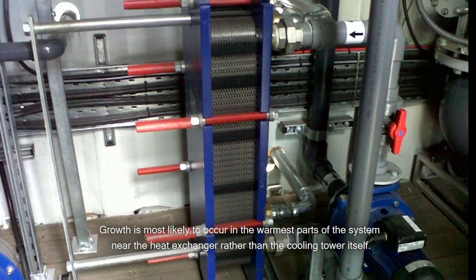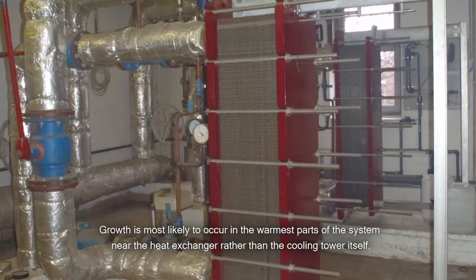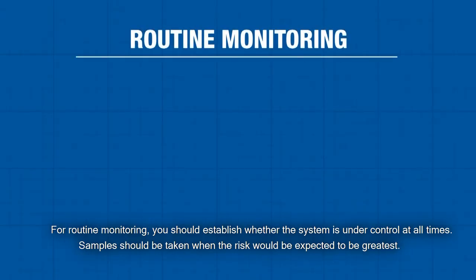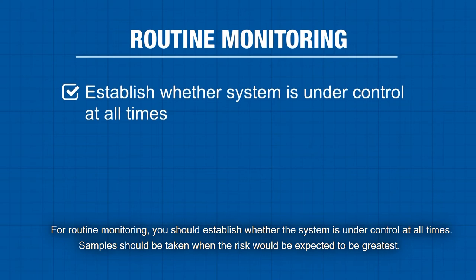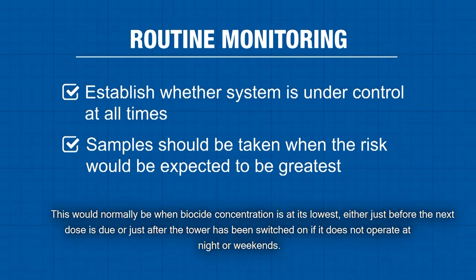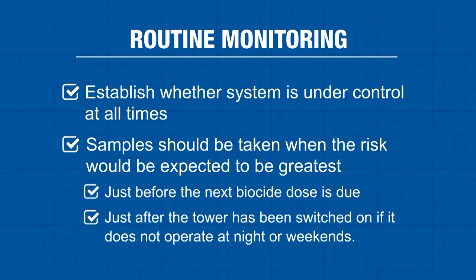Growth is most likely to occur in the warmest parts of the system near the heat exchanger rather than the cooling tower itself. For routine monitoring you should establish whether the system is under control at all times. Samples should be taken when the risk would be expected to be greatest — normally when biocide concentration is at its lowest, either just before the next dose is due or just after the tower has been switched on if it doesn't operate at night or weekends.